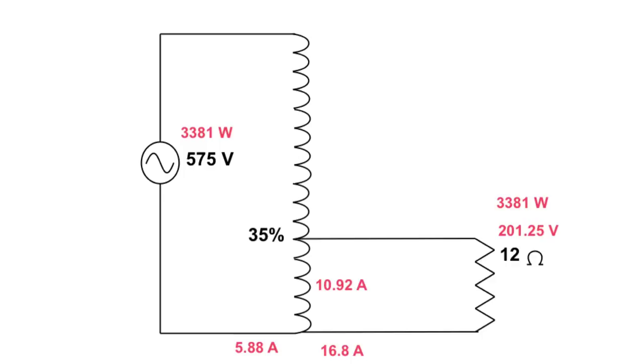And that's all you have to do for a step-down auto transformer. They're not that difficult. Again, just a quick walkthrough. You take the voltage, you multiply it by the tap setting, which gets us our voltage on this side. You take this voltage divided by the ohms of the load to get the current, which is 16.8 amps, through the load.